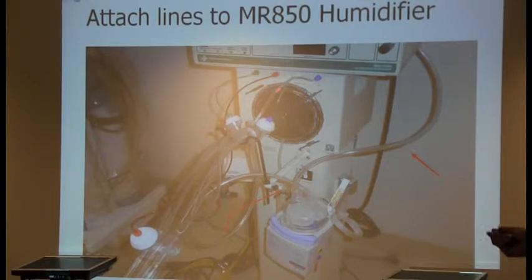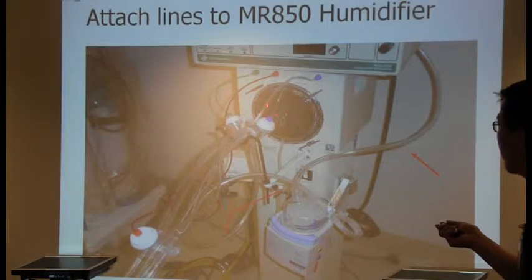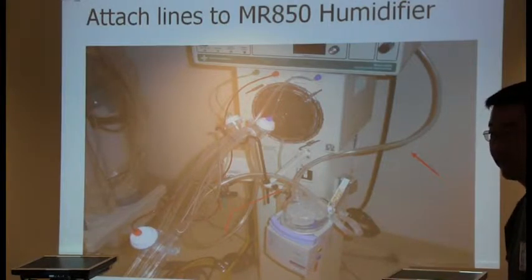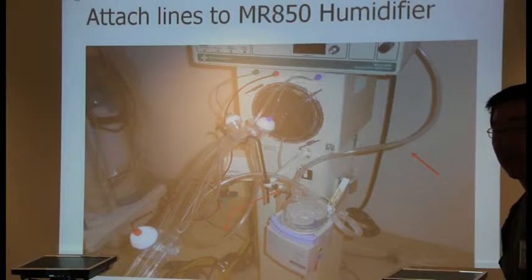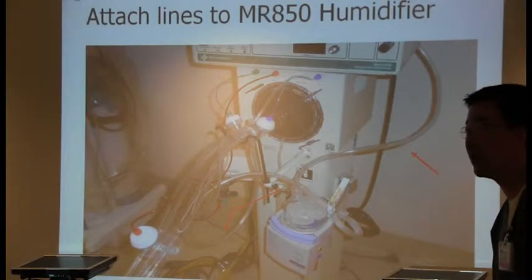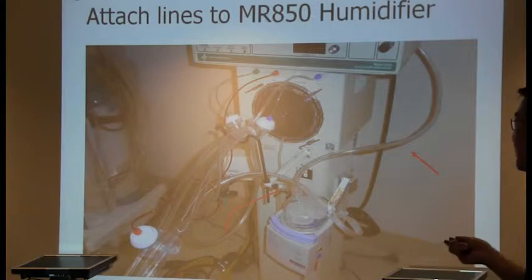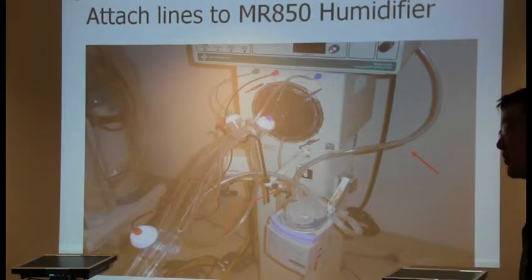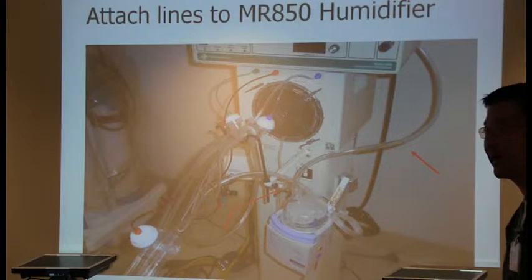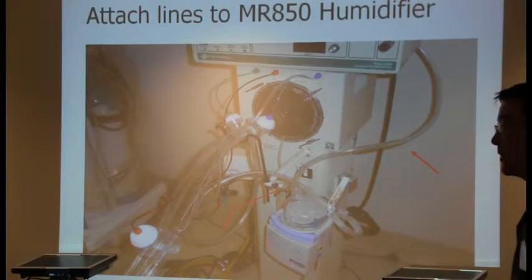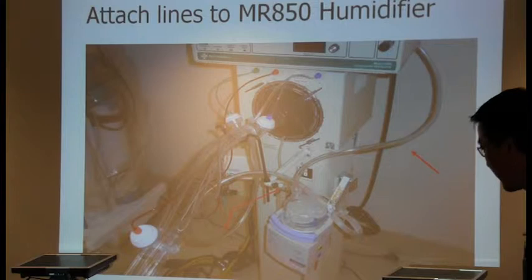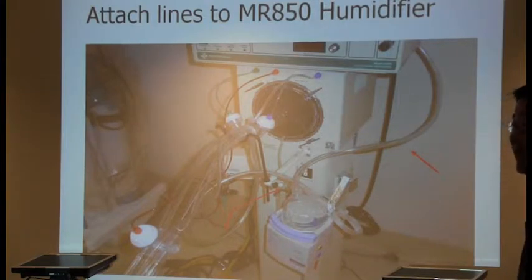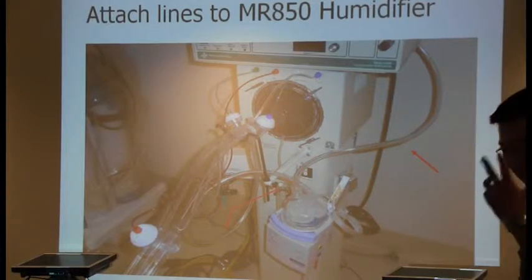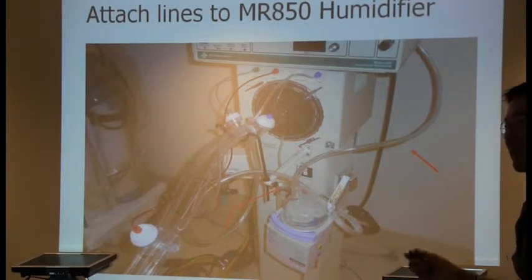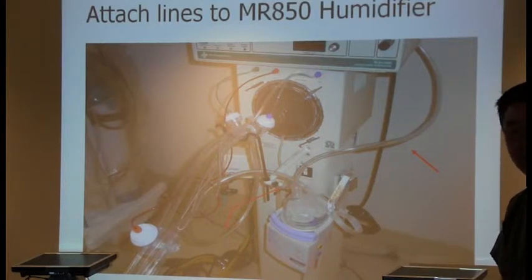Now here's the thing. If you were to reverse this crisscross, your ventilator will not work. That's the kicker. Your ventilator is going to give you some funky numbers, and it won't turn on. It won't do anything. That happened one time, and we're troubleshooting, and the therapist calls me and says, hey man, I can't get this thing to work, and we have a patient coming in. So I go up there, take a look at it, everything looks good, and next thing you know, I look down and go, oh, okay, yeah, I saw my lines crisscrossed. So once we undid that, everything worked.